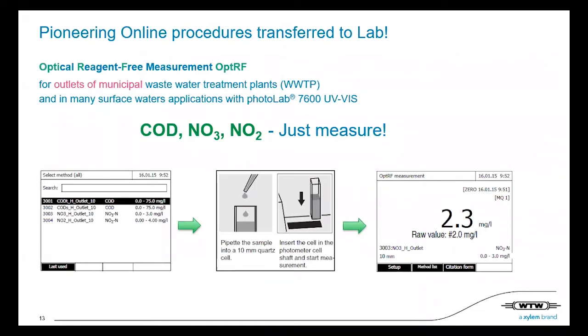But in municipal wastewater, it's an easy thing. You select the method like you select other methods. Then you just add a sample into a 10 millimeter quartz cell. Quartz cell is important because we are in the UV range. And then you just get a reading after 30 seconds. So this also works in some surface water.